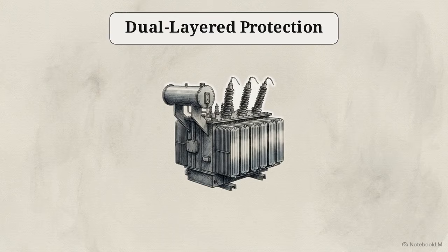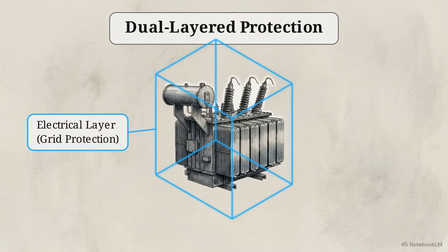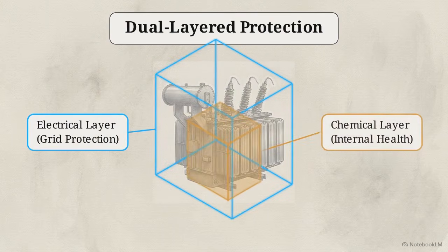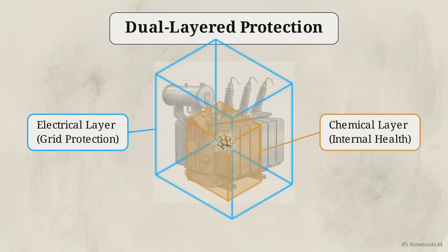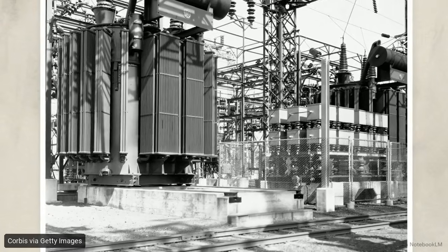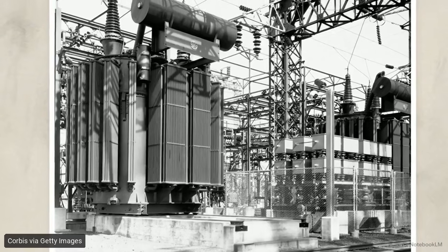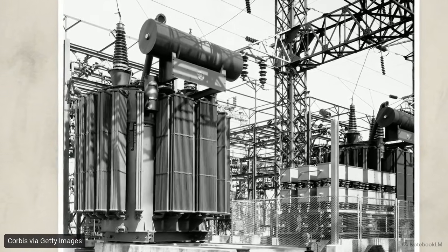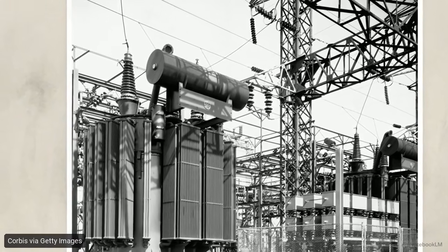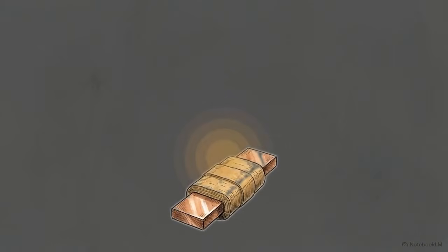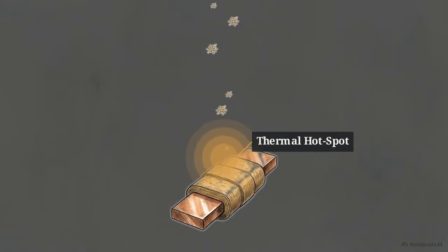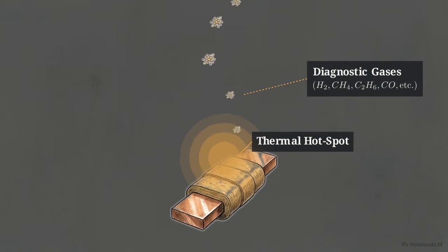To prevent this, engineers rely on a dual-layered protection architecture. They monitor both the electrical current and the internal chemistry of the transformer. Looking at the sheer scale of this vintage transformer tank, you can see the vast volume of dielectric oil inside. The first layer of defense involves identifying the physical and chemical symptoms of degradation within that oil pool, long before any electrical thresholds are crossed.